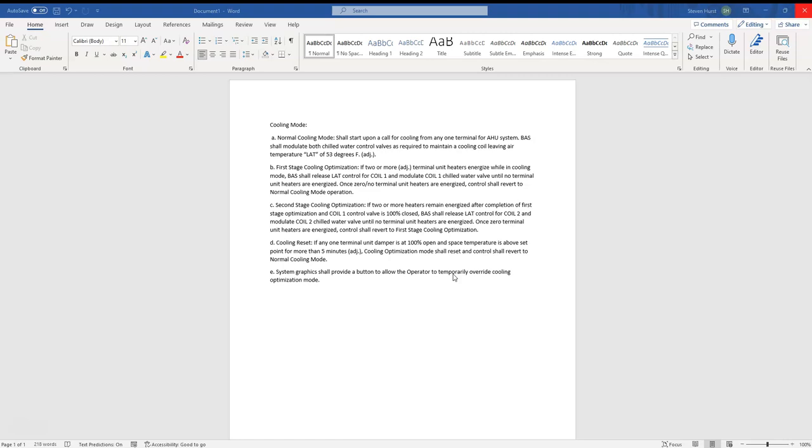The second stage is when coil one is all the way closed and there's still some VAVs that have heat going on. That's when coil two is going to release from controlling to discharge air temp and start turning down.